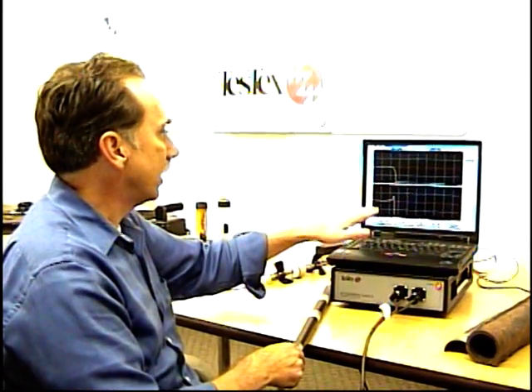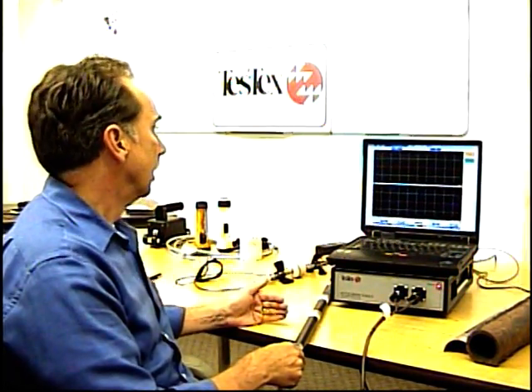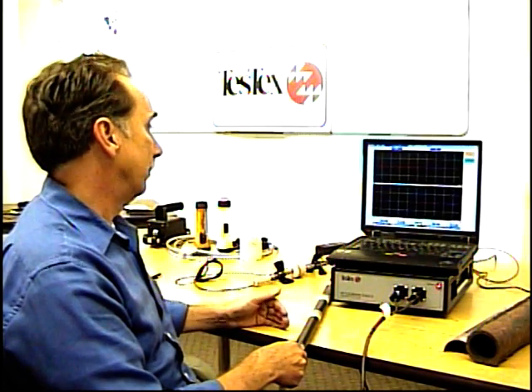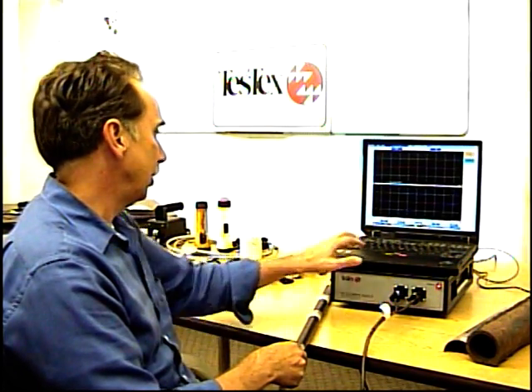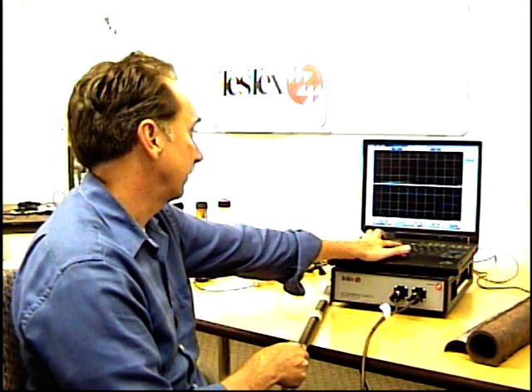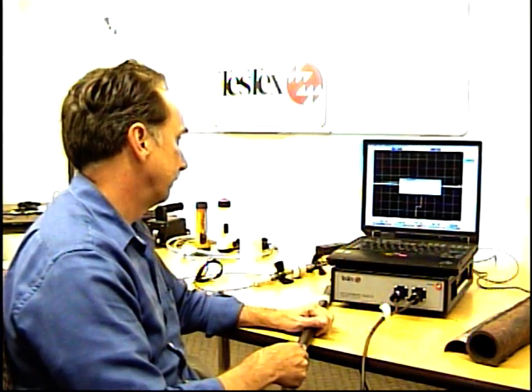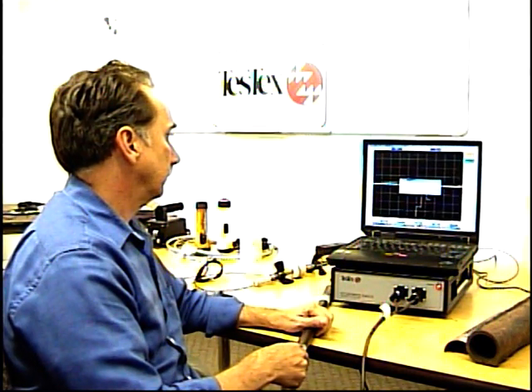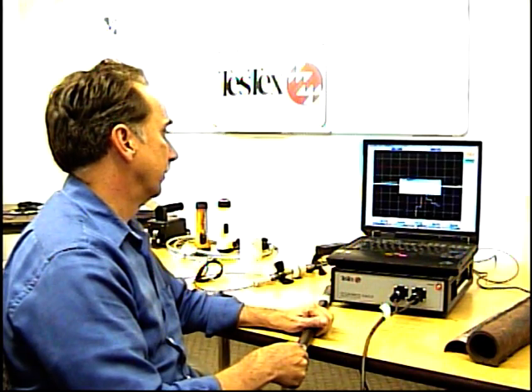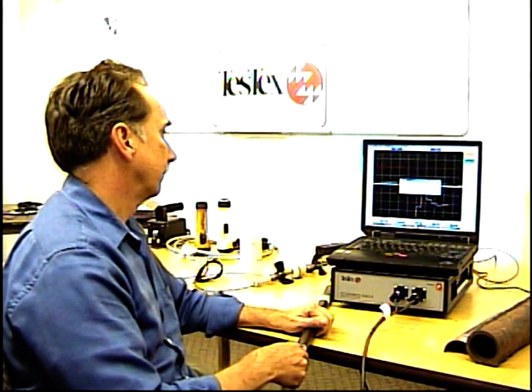Obviously, you could tweak it a little bit. You might want to go down to maybe 48 hertz. Okay, once you have that in the tube, still in a good section of the tube, you want to hit Control G. You want to gain the system again. You do not want to move the probe until it's done gaining.